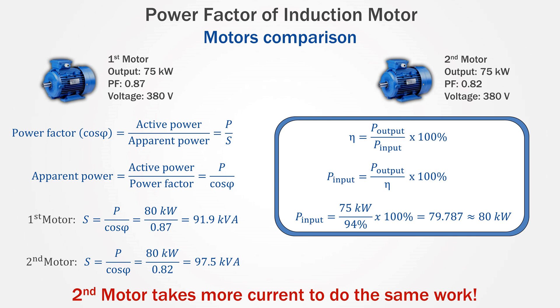Another way to look at it is that at 82% power factor, the second motor takes more current to do the same work. More current means greater conductor size, so it's going to cost more. More current causes more copper losses, which results in poor efficiency. And more current causes greater voltage drops in power supply equipment, which will cause equipment to not function properly or at all.